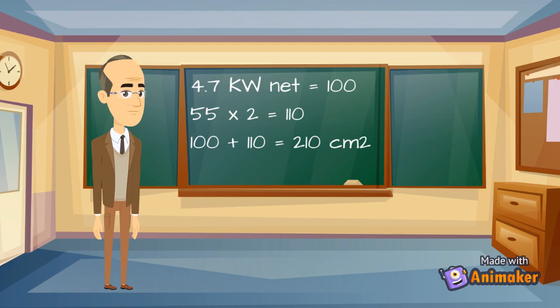Our appliance is 4.7 kilowatts net. We must add 55 centimeters squared for every kilowatt over 2.7 kilowatts. Which equals 110 centimeters squared. We add this to the 100 centimeters squared which we started with.